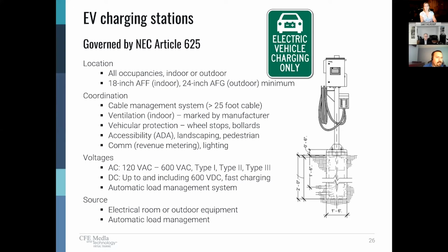If you've got a cabling system that's over 25 foot in length, you need a cable management system per code. If you've got an indoor installation, one consideration is ventilation. Some manufacturers, and this will be marked on the equipment, require ventilation for off-gassing, and there's a specific requirement in code that the manufacturer mark their equipment if that's required. So that's a consideration. And then vehicular protection, whether you're indoor or outdoor, you need a way to prevent the vehicle from coming in contact with the equipment, whether that's wheel stops or bollards or some other protection means.